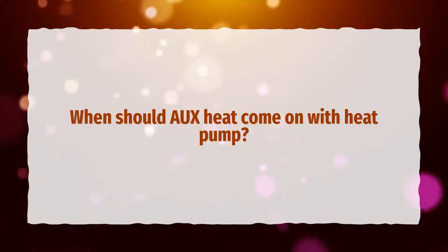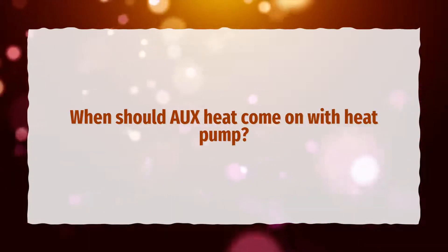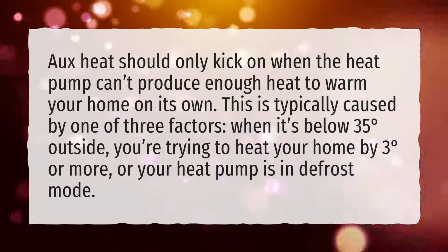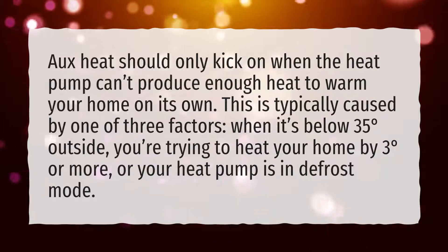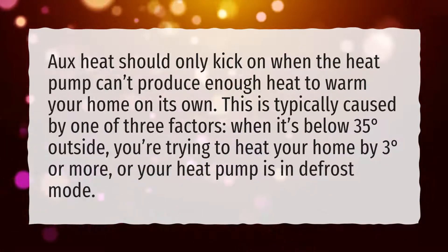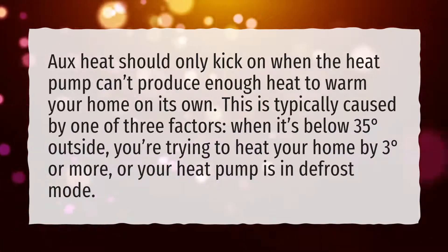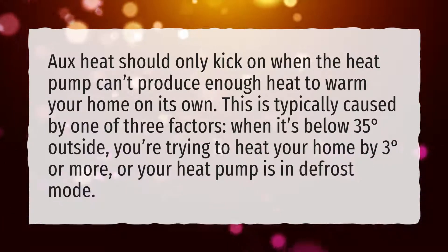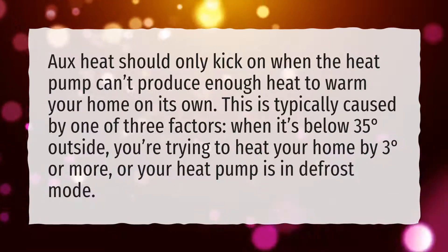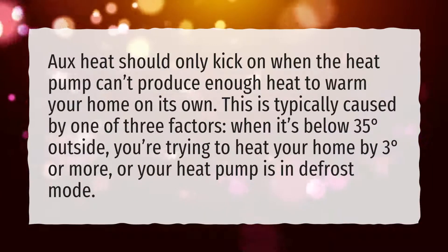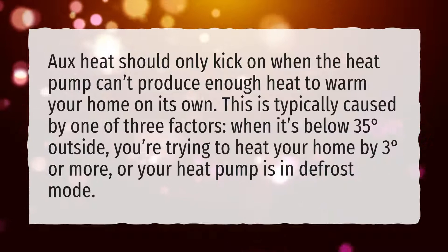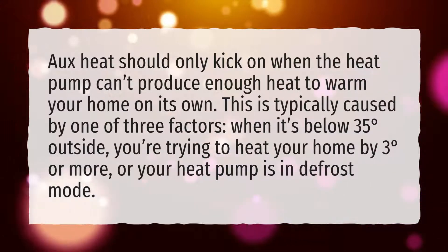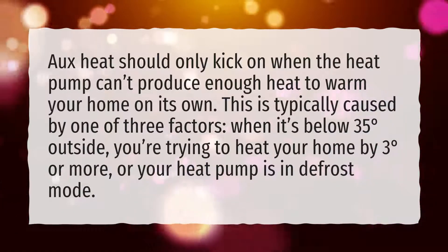When should aux heat come on with a heat pump? Aux heat should only kick on when the heat pump can't produce enough heat to warm your home on its own. This is typically caused by one of three factors: when it's below 35 degrees outside, you're trying to heat your home by 3 degrees or more, or your heat pump is in defrost mode.